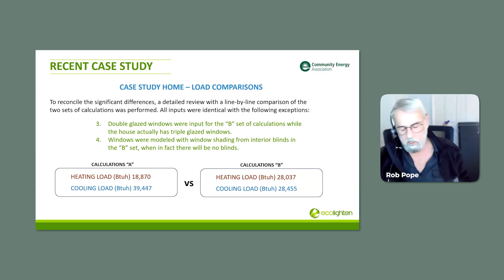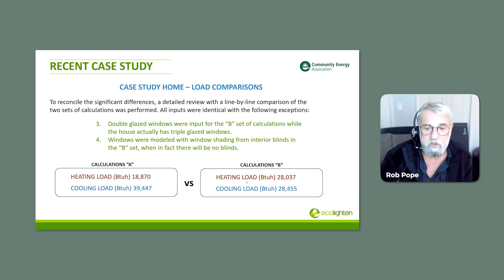So let's look at this again: 18,000 BTU to 28,000 BTU, obviously not going to work. 39,000 BTU down to 29,000, 28,000 BTU, also not going to work. They're going to have to change out the equipment and the ducting. There's no way around that.